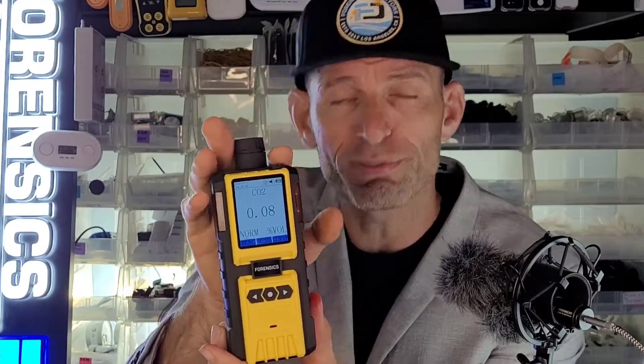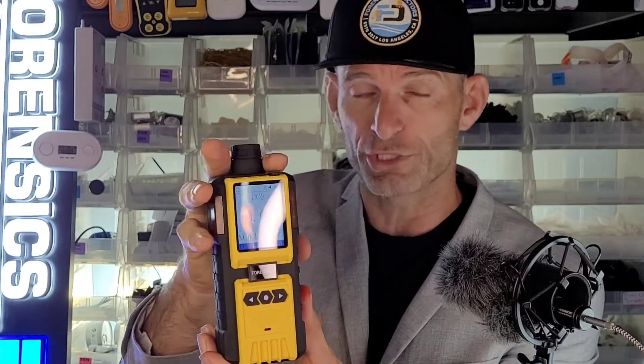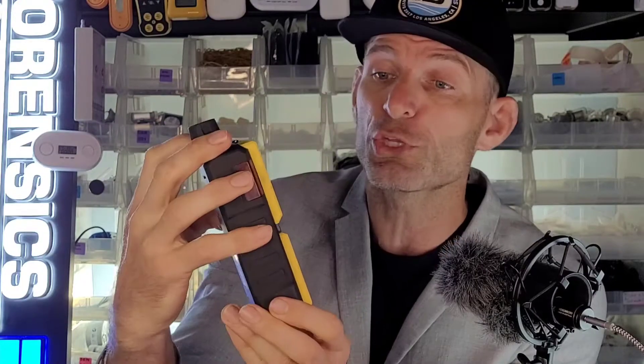Now don't get confused with our zero to 100 percent volume carbon dioxide analyzer. It's a different range — when we're talking about very high levels of carbon dioxide for industrial process or for exhalation of breath and things like that, you need the percent volume range. For air quality measurements — zero to a thousand, zero to five thousand — you need the ppm range.